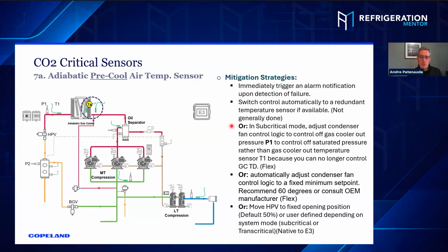So what other mitigation strategy can you have? If you're in subcritical mode, you can adjust condenser fan speed to control off gas cooler pressure, P1. So you're controlling off of minimum gas cooler pressure, off the saturation temperature rather than the gas cooler out, because if you lose this sensor, you can't calculate TD from those 2 points. So you're going to have to default to a minimum pressure, and that can be done using a flex combiner.